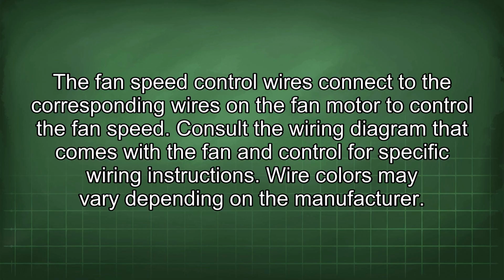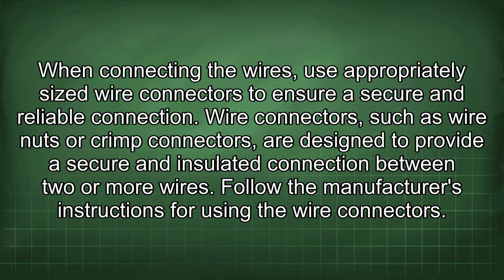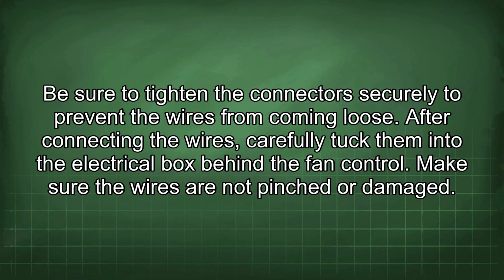Consult the wiring diagram that comes with a fan and control for specific wiring instructions. Wire colors may vary depending on the manufacturer. When connecting the wires, use appropriately sized wire connectors to ensure a secure and reliable connection. Wire connectors, such as wire nuts or crimp connectors, are designed to provide a secure and insulated connection between two or more wires. Follow the manufacturer's instructions for using the wire connectors. Be sure to tighten the connectors securely to prevent the wires from coming loose.